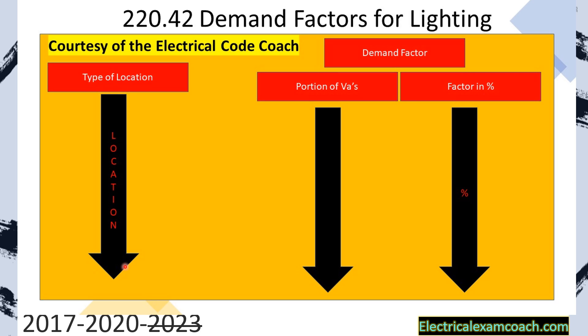So if it's not listed inside of this type of occupancy, we're going to cross over. And if you look over here down in the bottom right hand, it's at 100% calculation, meaning that there is no demand factor for lighting unless you're one of these specific places that are listed on the left. Then over here across the top, we find our demand factor.